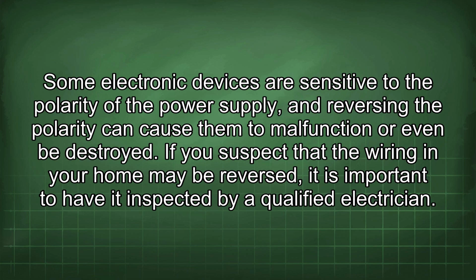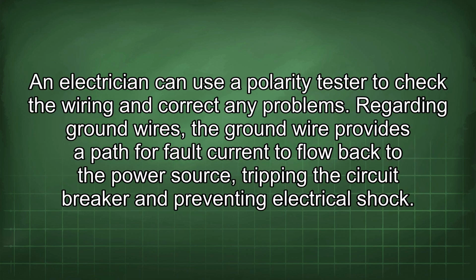If you suspect that the wiring in your home may be reversed, it is important to have it inspected by a qualified electrician. An electrician can use a polarity tester to check the wiring and correct any problems. Regarding ground wires, a ground wire provides a path for fault current to flow back to the power source, tripping the circuit breaker and preventing electrical shock.